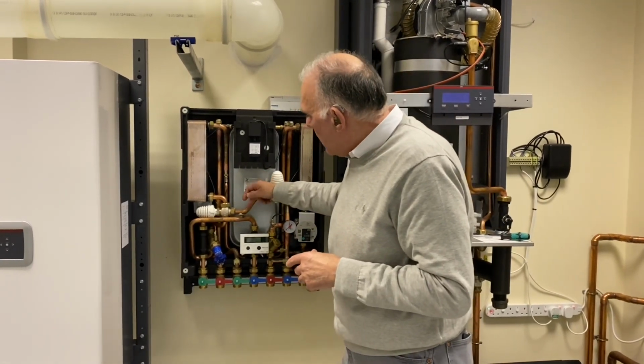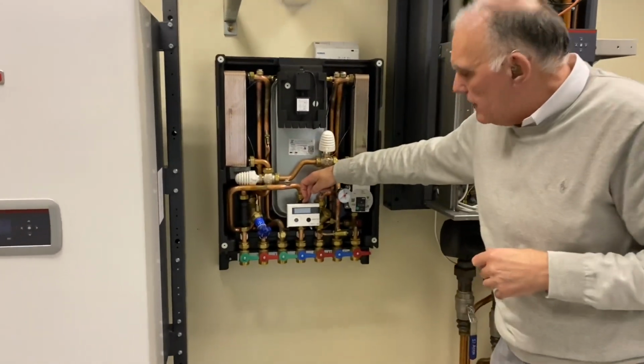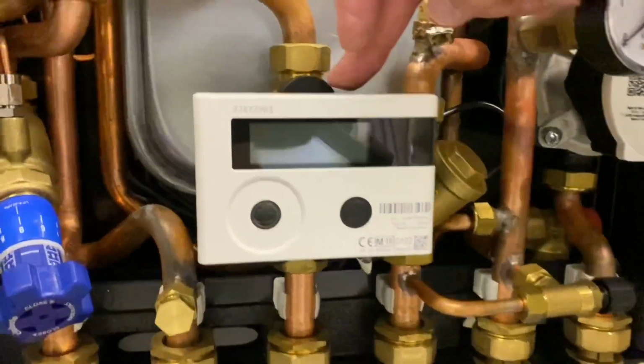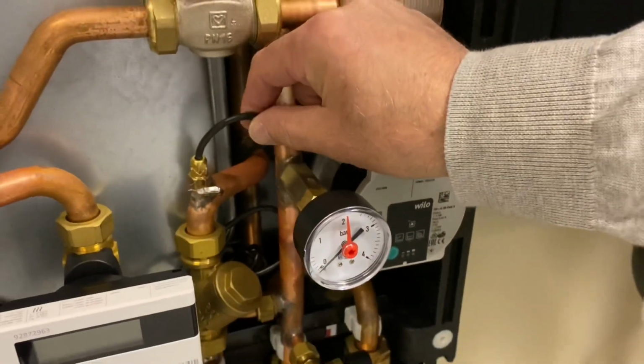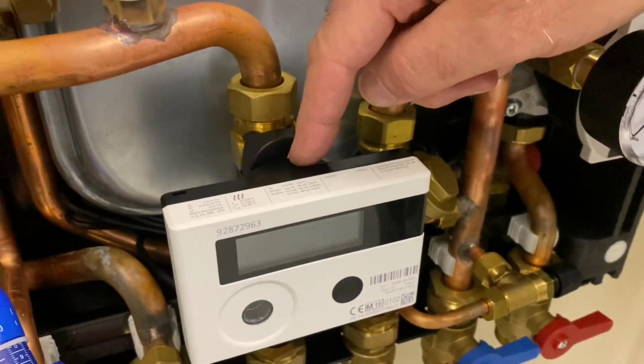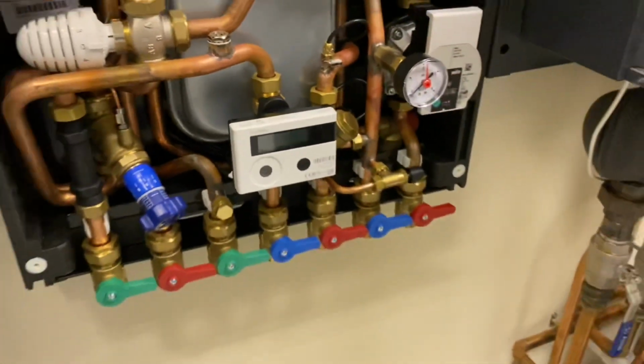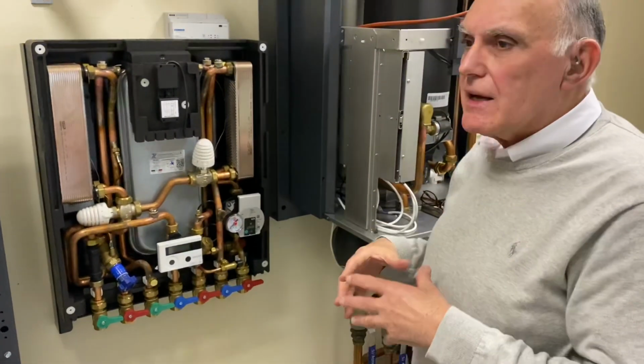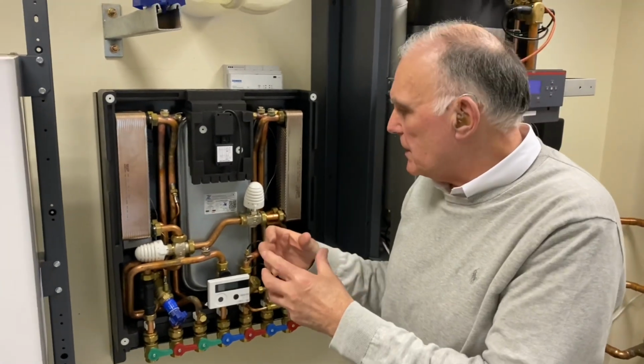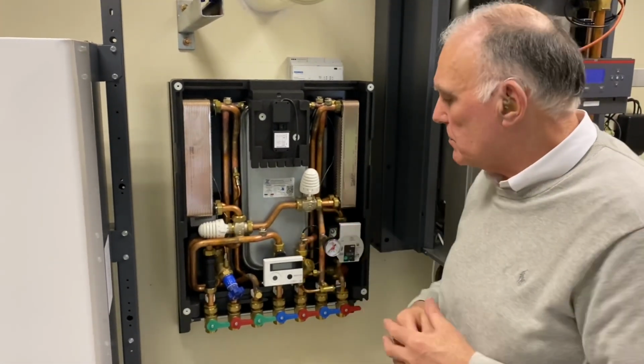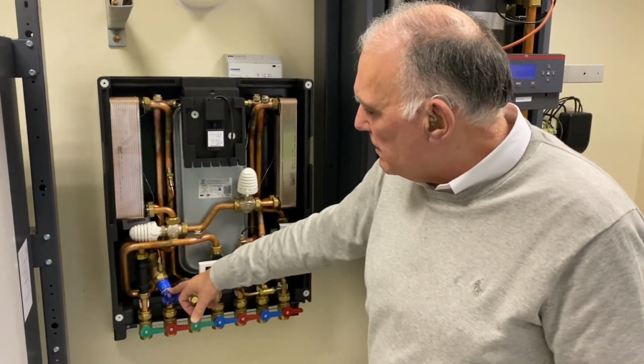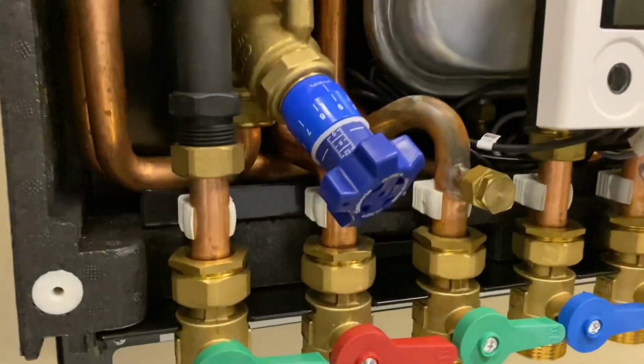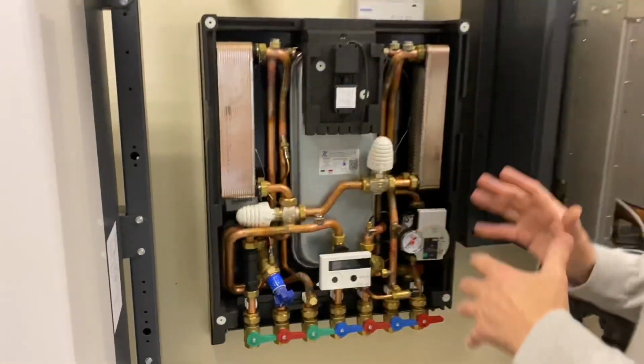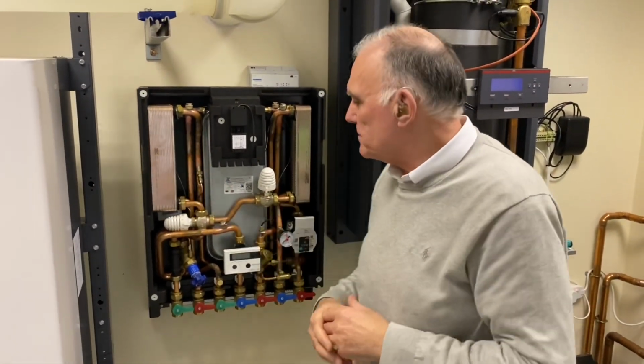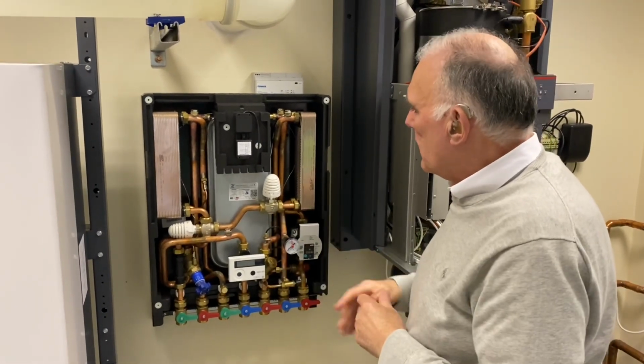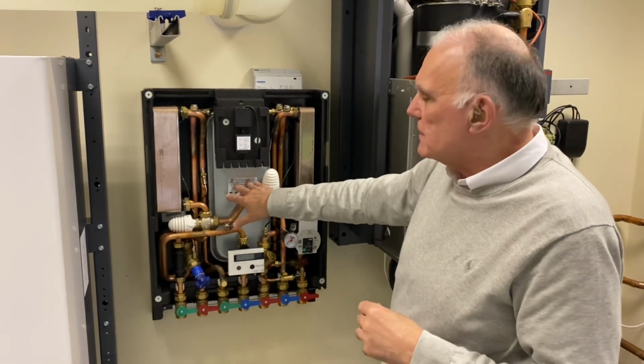The return waters are taken through this device here. This is the heat meter. So what we've got is a flow temperature coming in, the return temperature sensor, which is at the back of the heat meter, and there's also a flow meter. And with those figures, it can calculate the amount of energy consumed by that property. So the customer will pay for what they use. There's also a differential pressure valve here, and what that's used for is to balance each heat meter, the flow return through each heat meter in the block, so each one is apportioned the right flow. HIU unit. Expansion vessel is here for the space heating system.